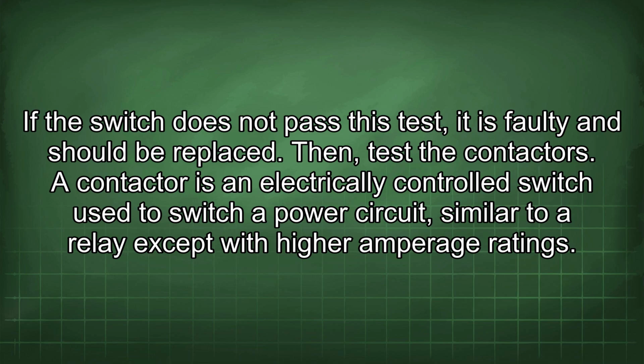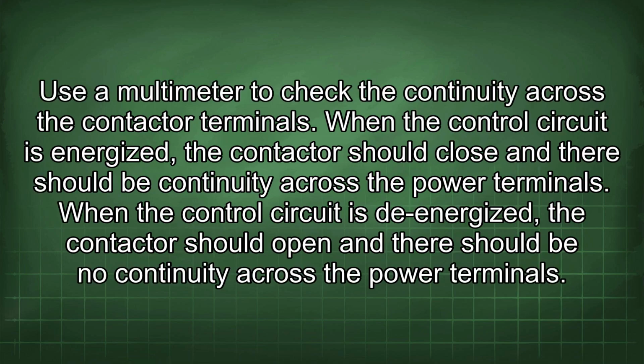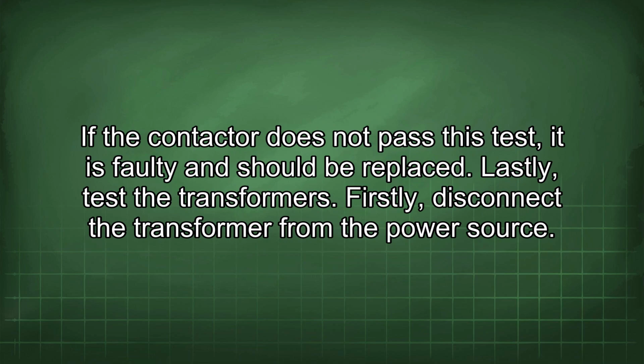Then test the contactors. A contactor is an electrically controlled switch used to switch a power circuit, similar to a relay except with higher amperage ratings. Use a multimeter to check the continuity across the contactor terminals. When the control circuit is energized, the contactor should close and there should be continuity across the power terminals. When the control circuit is de-energized, the contactor should open and there should be no continuity across the power terminals. If the contactor does not pass this test, it is faulty and should be replaced.